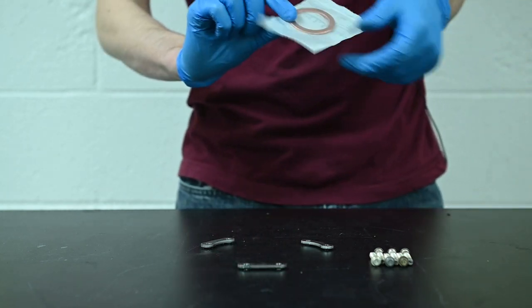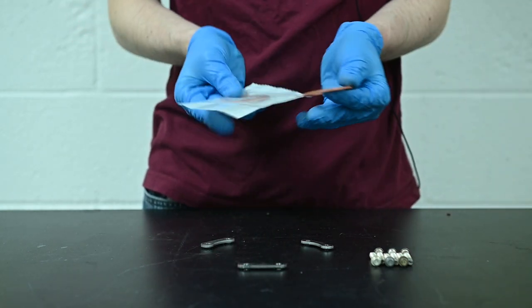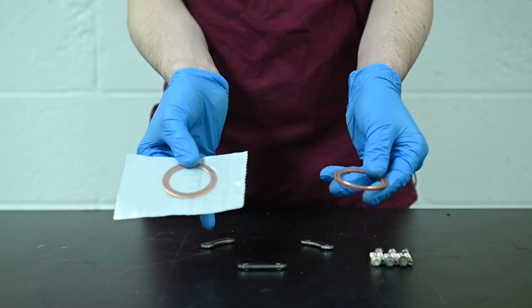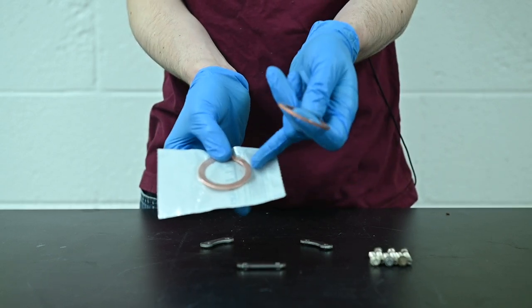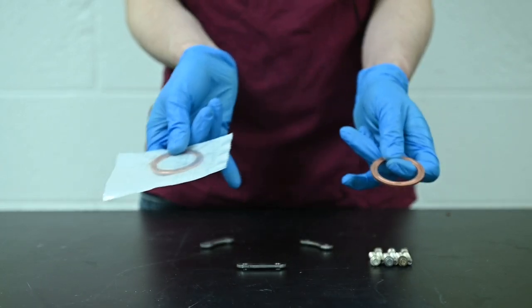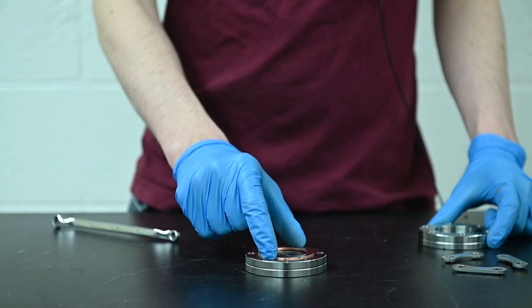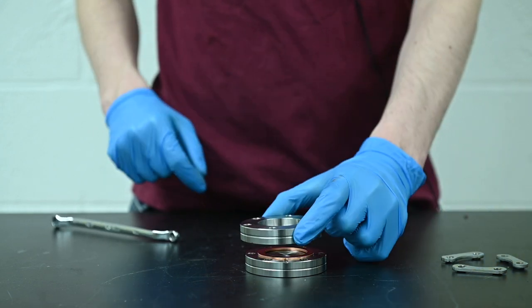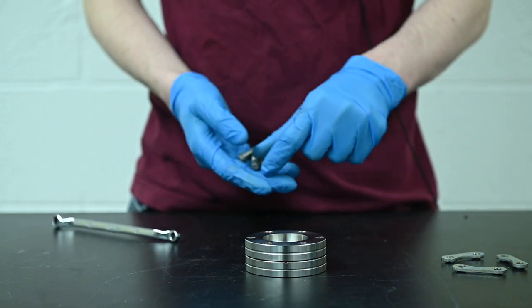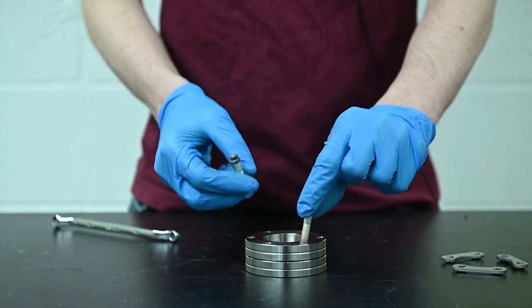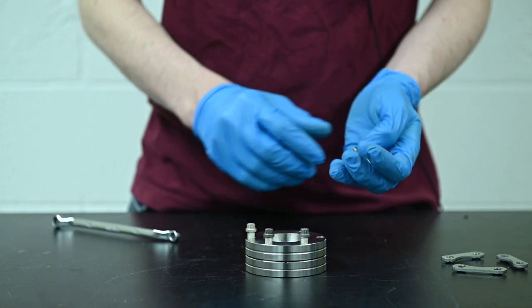Copper gaskets come in a sealed bag to protect them from environmental contamination. In order to assemble a conflat flange, carefully remove the copper gasket from the sealed bag, place it between two flanges, and then use 12-point silver-plated hardware to connect the two flanges together. The silver plating is important to reduce friction and prevent galling of the fasteners.